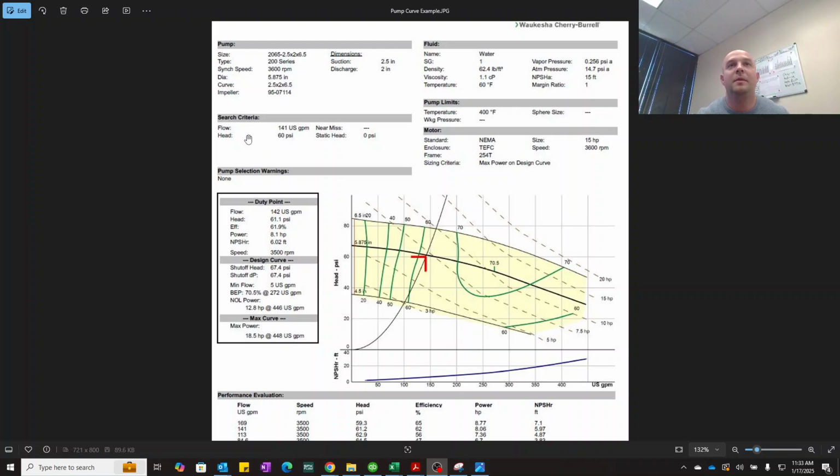Now, where does that 60 psi come from? That's our discharge head. Most of that in most systems is going to be because of either obstruction downline, maybe a filter, some point of loss, but more commonly it's the friction loss, right?